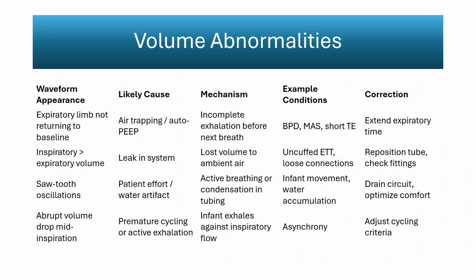When inspiratory volume exceeds expiratory volume, the loop reflects lost volume rather than retained volume. Neonates ventilated with uncuffed tubes or loose circuit fittings frequently lose a portion of the delivered breath to ambient air. This appears as a gap between the inspiratory and expiratory limbs. Correcting the leak restores symmetry and ensures the displayed tidal volume represents what the infant actually receives.